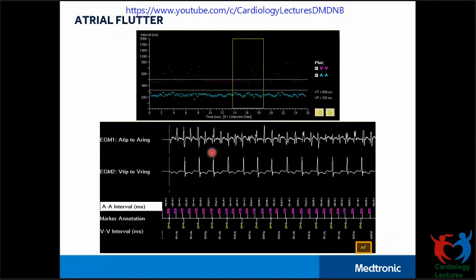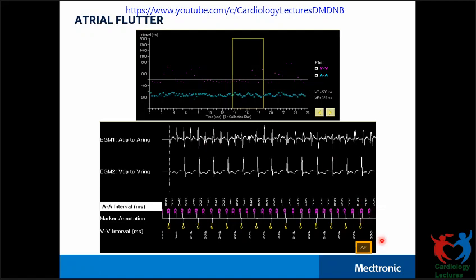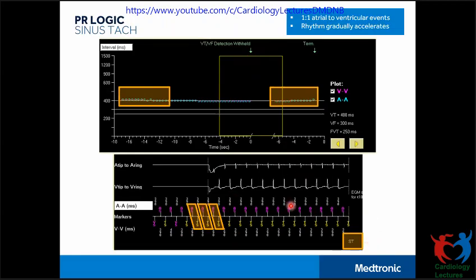In the second example, looking at the plot again, atrial rates are faster than the ventricular rate. Looking at the EGM, atrial rates are higher than ventricular, but for every ventricular interval we consistently see two P waves. This allows the device to call this out as atrial flutter and withhold detection for that particular episode.